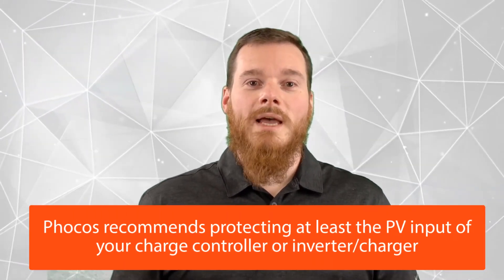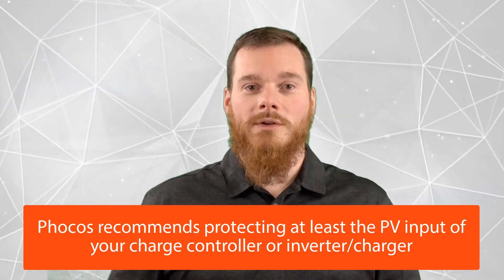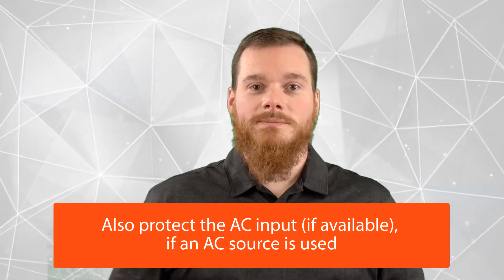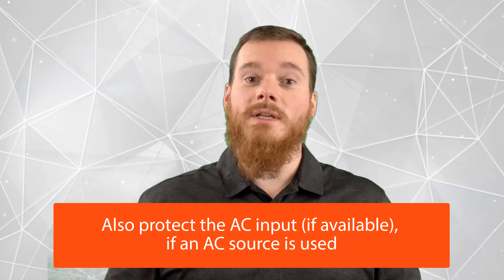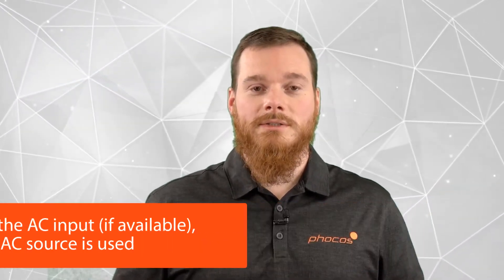At Phocos, we recommend protecting at least the PV input of your charge controller, or your inverter charger, and, if available in your system, your AC input. You only need to protect the AC input with an SPD if you are really connecting to an AC source, such as a generator, or a public grid.